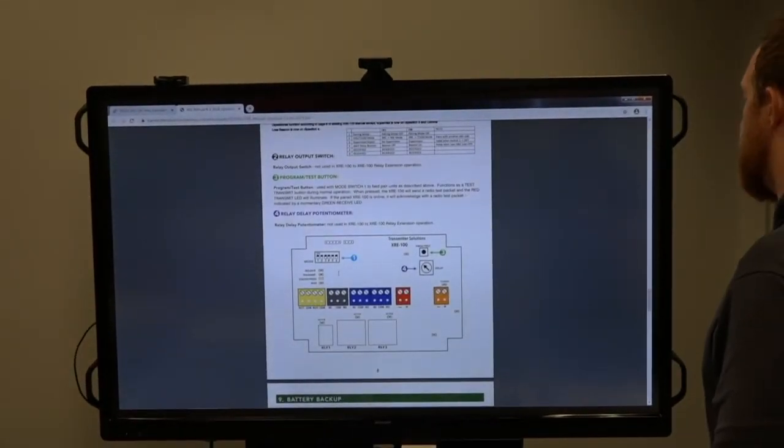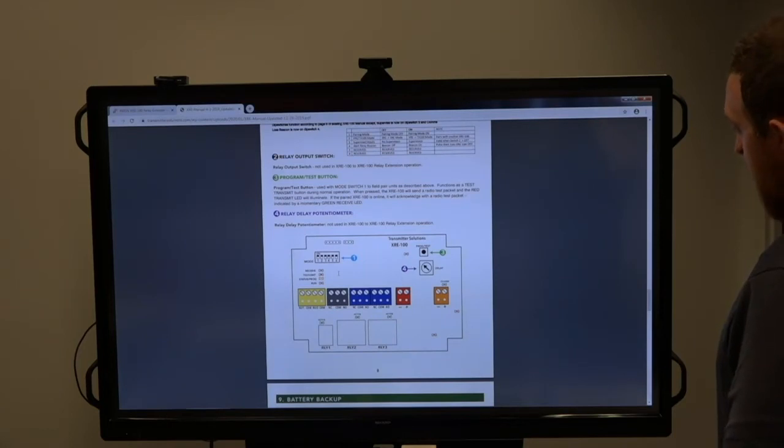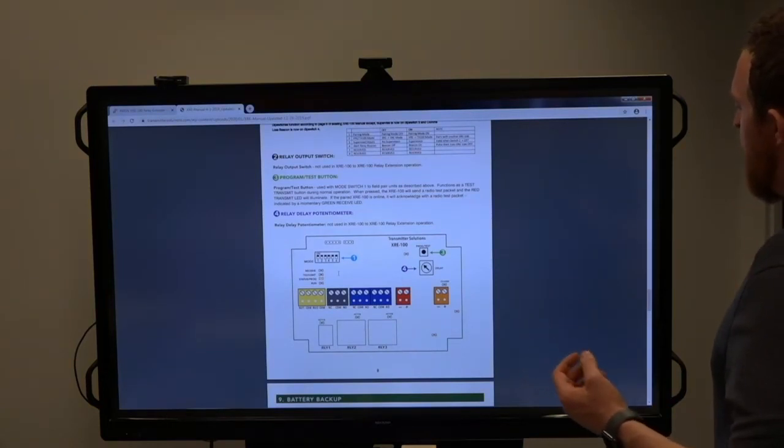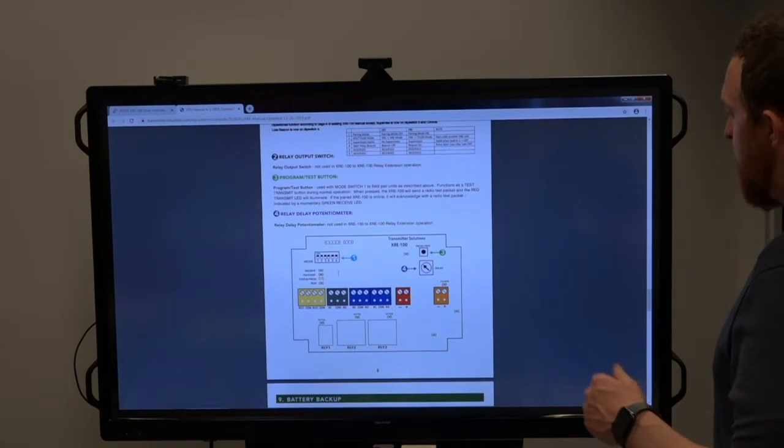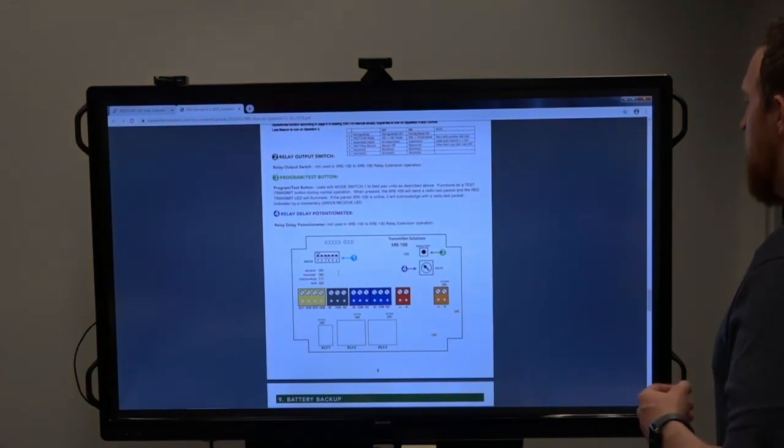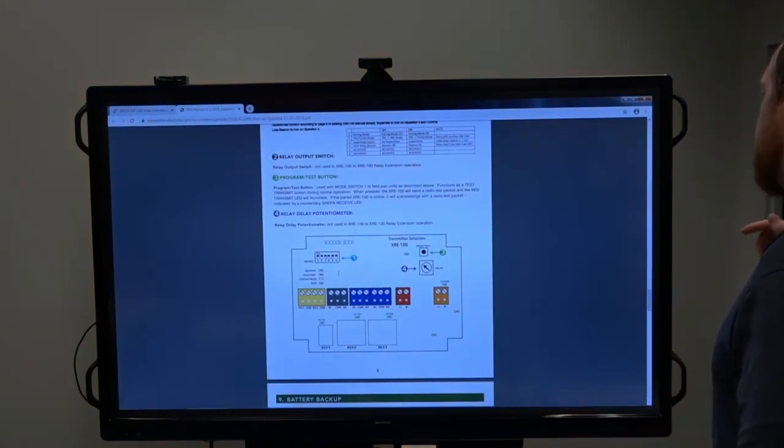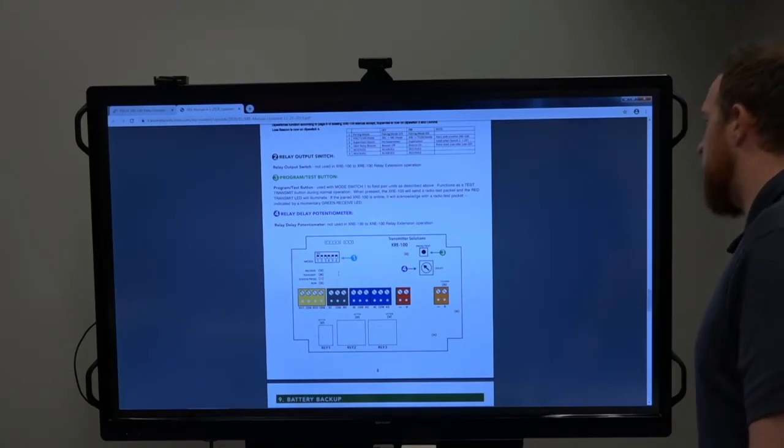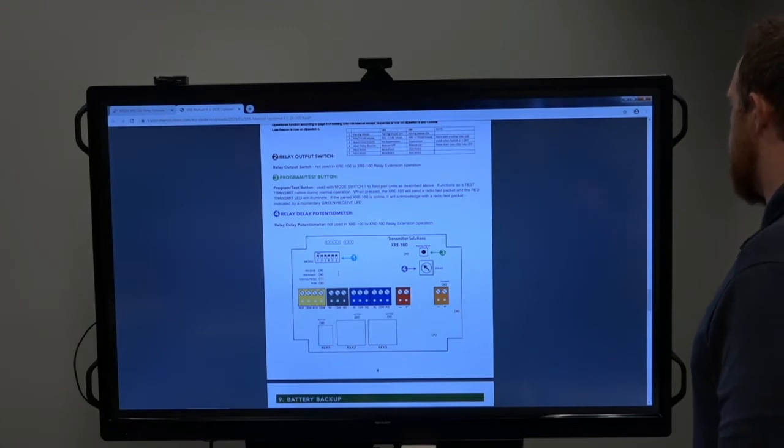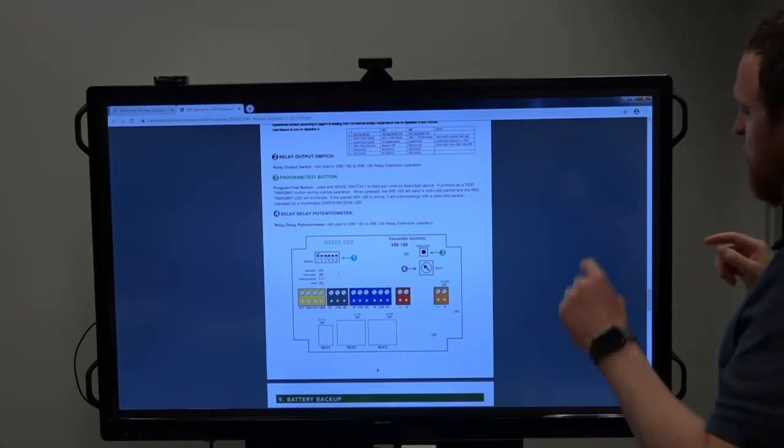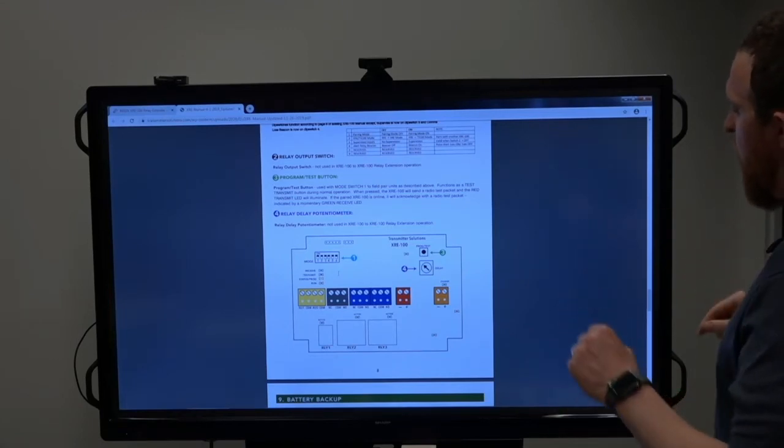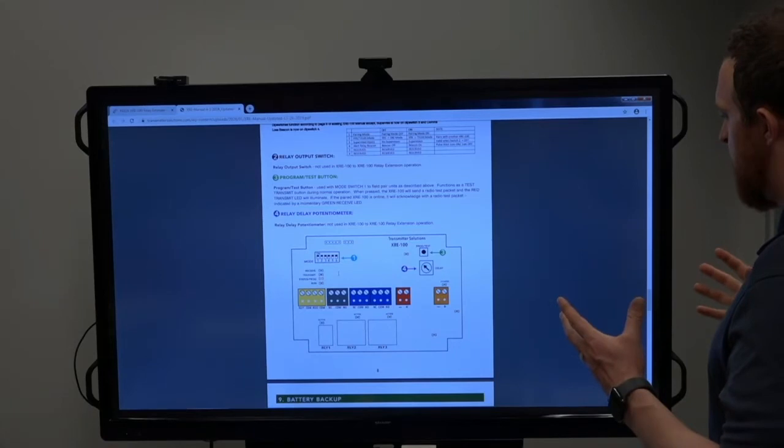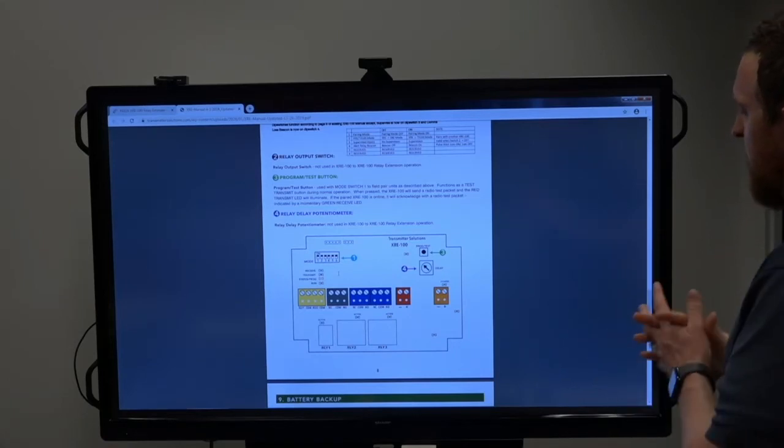On the top right hand corner, we have a program or test button. These devices do not come paired. So when you get them, all you have to do is turn on DIP switch one, which is in the top left hand corner, of both devices, and then on one of the devices, press the program test button, which you can see in the top right hand corner. It's going to go through a series of blinks, and then they're communicating. You turn DIP switch one off in both devices, and now you're in normal operation.